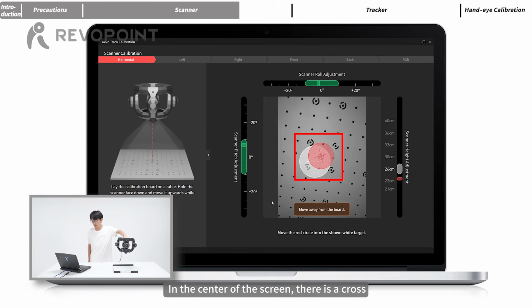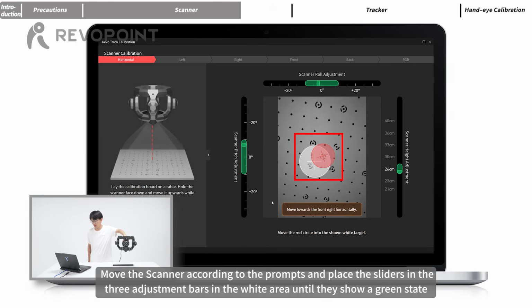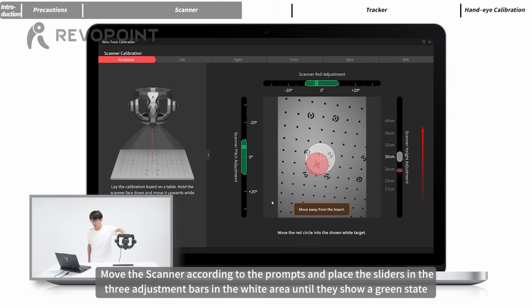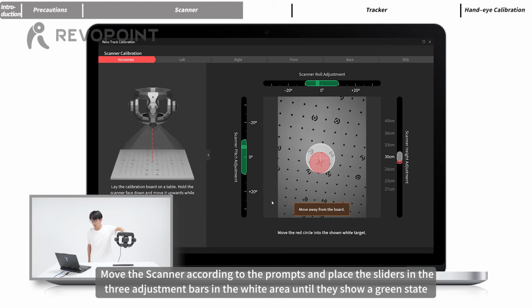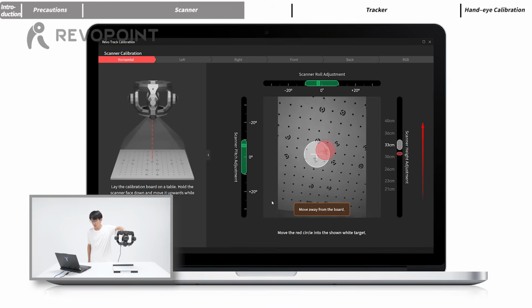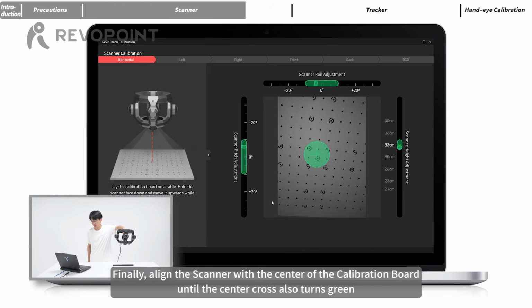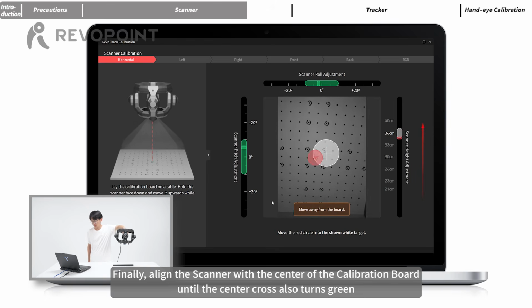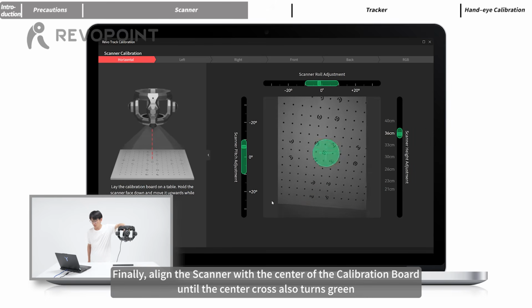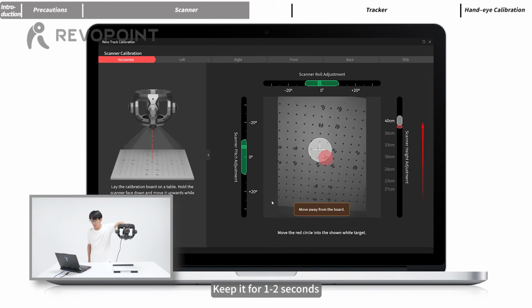In the center of the screen, there is a cross. Move the scanner according to the prompts and place the sliders in the 3 adjustment bars in the white area until they show a green state. Finally, align the scanner with the center of the calibration board until the center cross also turns green. Keep it for 1 to 2 seconds.